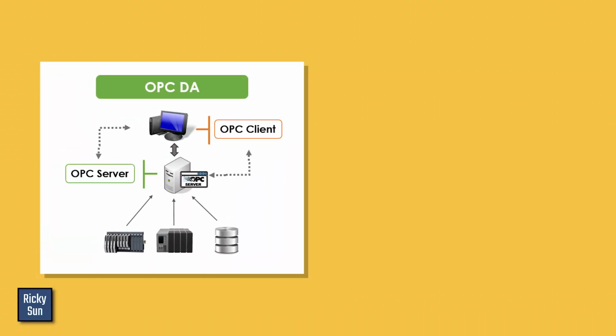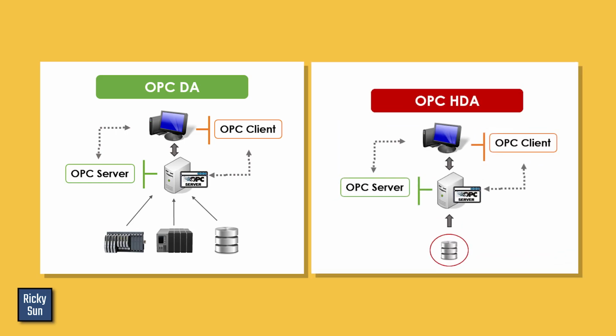We are going to switch from the old to the new. We have two environments, both collecting data from CygNet OPC servers, one collecting from OPC DA and the other from OPC HDA. So we have two instances of the interface trying to collect the same data from the same data source. Well, it's not the same data source. One is DA, one is HDA.